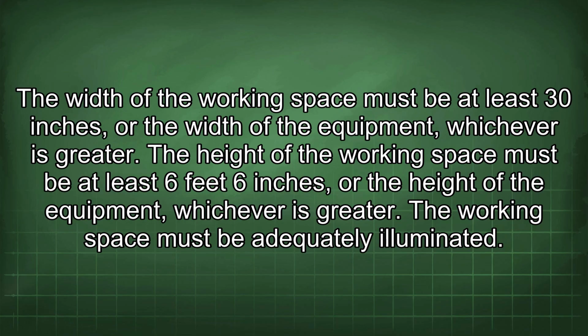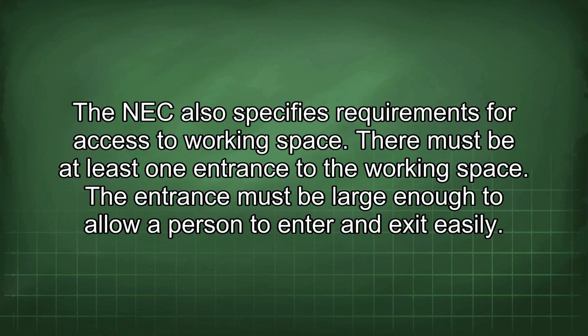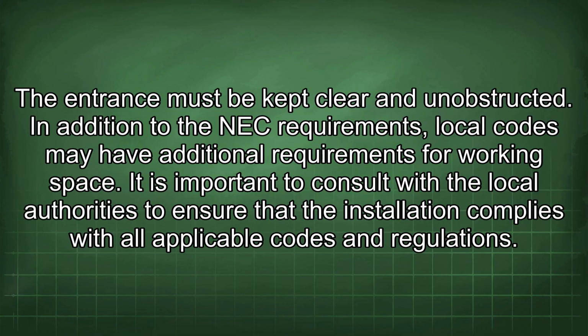The width of the working space must be at least 30 inches, or the width of the equipment, whichever is greater. The height of the working space must be at least 6 feet 6 inches, or the height of the equipment, whichever is greater. The working space must be adequately illuminated. The NEC also specifies requirements for access to working space. There must be at least one entrance to the working space. The entrance must be large enough to allow a person to enter and exit easily. The entrance must be kept clear and unobstructed.